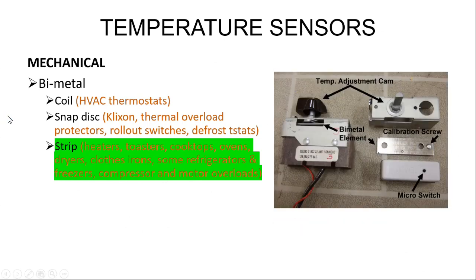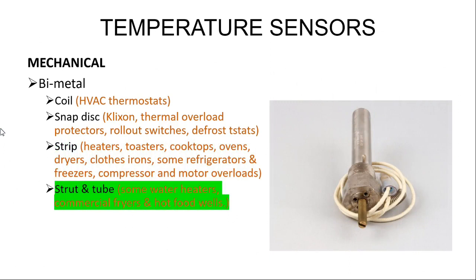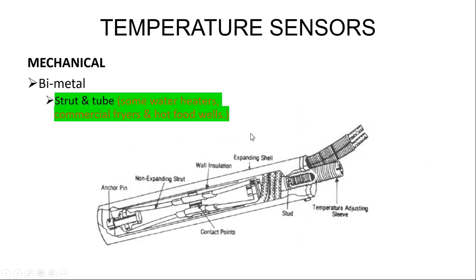Here's another example of the bimetal strip. This is enclosed. There's a knob, stem with a calibration screw right there, and a microswitch that's operated by the bimetal strip. Strut and tube. It's not a common item, but they are in use in some water heaters, commercial fryers, and hot food wells. They're known to be rather expensive, but also known to be the most accurate mechanical control on the market. The strut and tube is comprised of two basic parts: the outer shell, made of high expanding metal, and the strut assembly, made of low expanding metal.